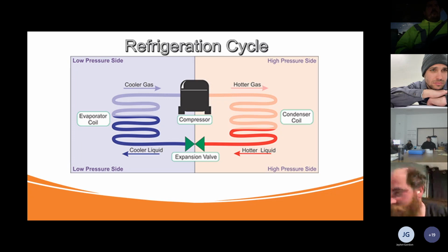I mean, Shane, go ahead, and then we'll address Travis's question. I was going to say that some condensers, not all, but there's an accumulator right before the compressor too. That thing's job basically is to trap liquid and only suck the boiled off vapor refrigerant out of the top of the can. So sometimes if you've got an accumulator too, correct me if I'm wrong, you don't have to worry so much about liquid getting into the compressor, so long as you don't fill the jar full.